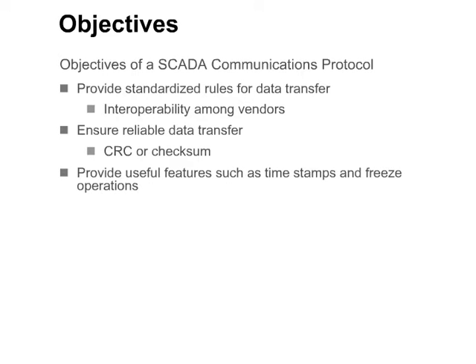A SCADA communications protocol is likely to need to support advanced features such as timestamp data or freeze operations. Freeze operations allow remote devices to report data as of a specific time or event, regardless of when the data are actually read.